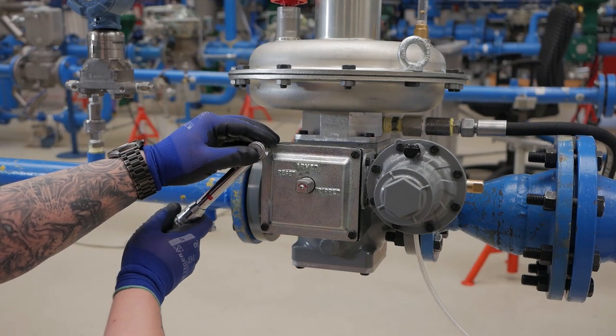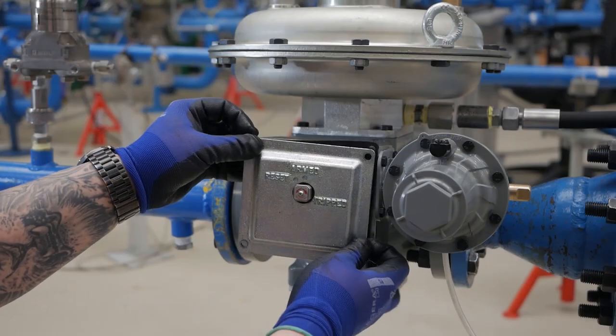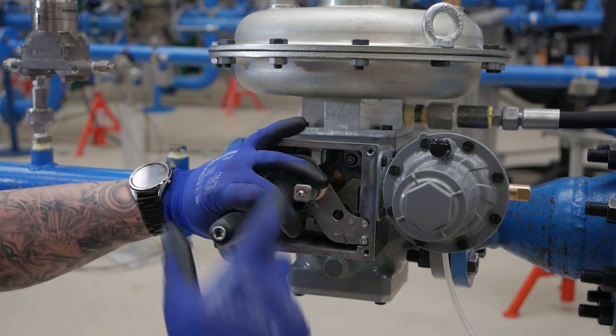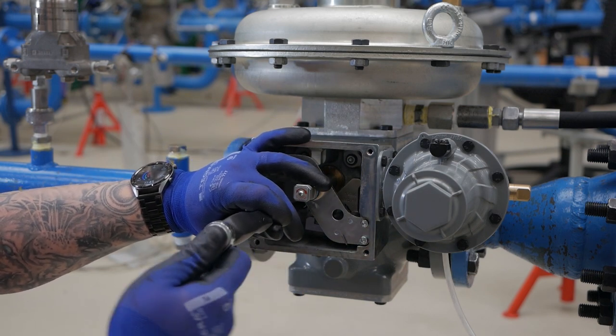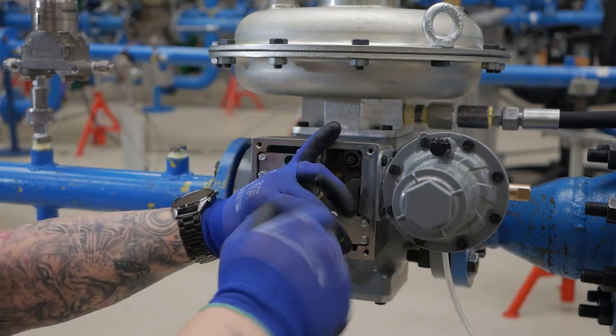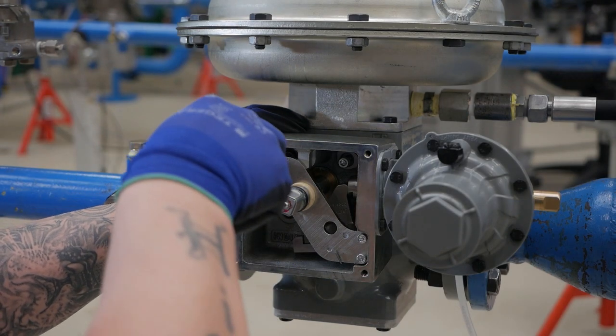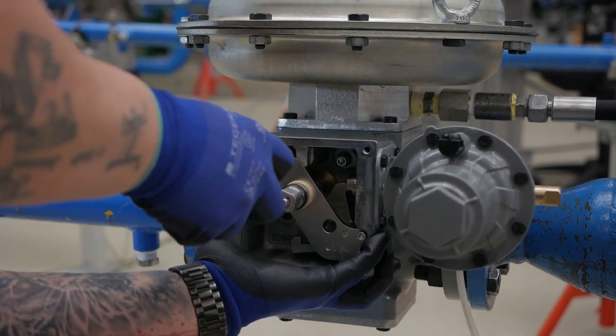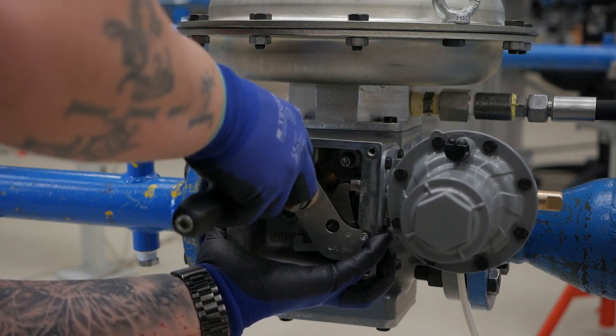Remove the slam-shut box cover by backing out the four bolts with a 10 millimeter socket. Once the cover is removed, remove the four hex socket screws — key 224 on the drawing in the instruction manual — using a 5 millimeter allen head. Once the bolts are removed, the entire slam-shut assembly can be removed from the body. Pull directly out, being careful of the o-ring seals. Set aside in a safe place, protecting the o-rings.